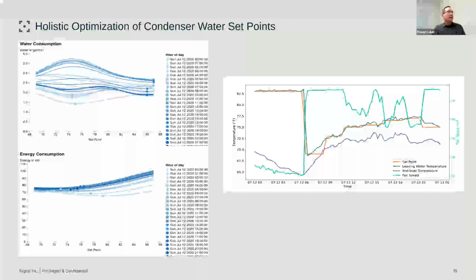This is actual data from a smaller system. If you have a loop where you consume water through evaporation in the cooling towers and electricity for running the fans, and most importantly for running a compressor and a chiller, plus the pumps that move water between these, then we can model, under any of the given set point choices on the x-axis, and for the different times of day we have data for, how these take on very different shapes.